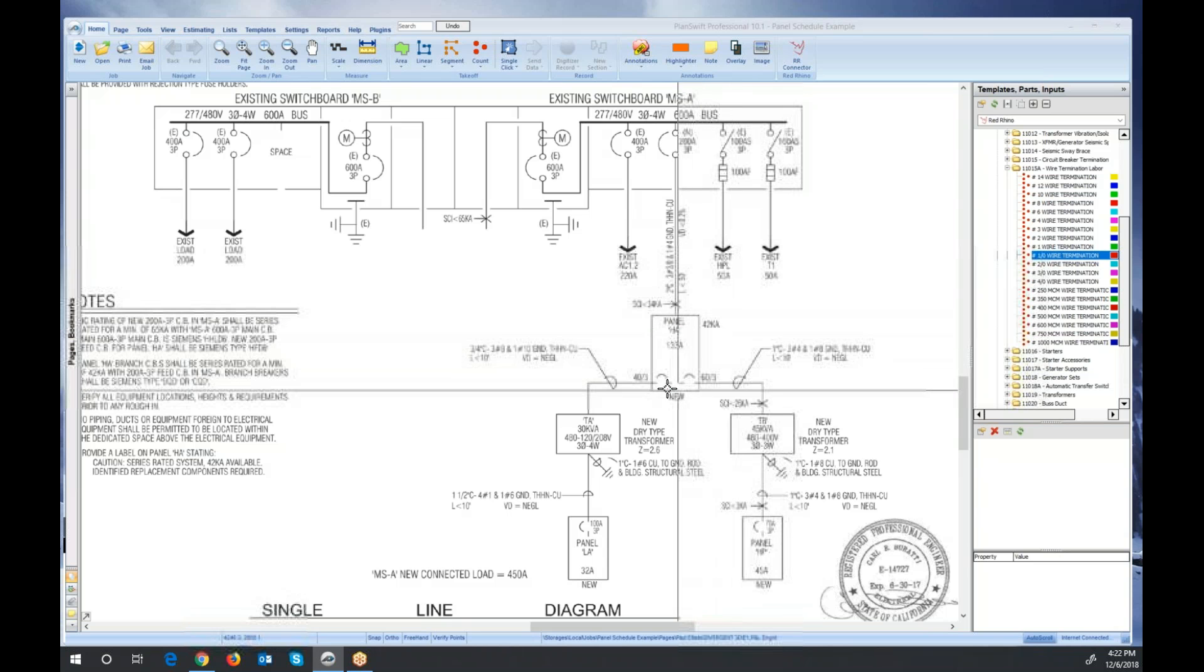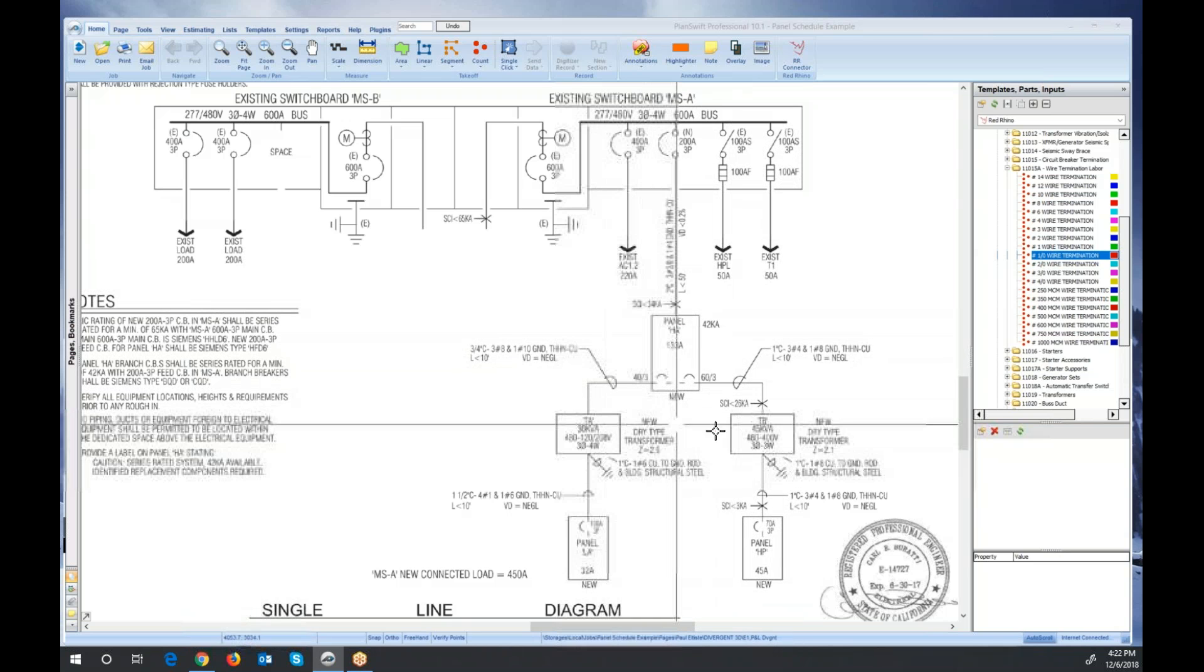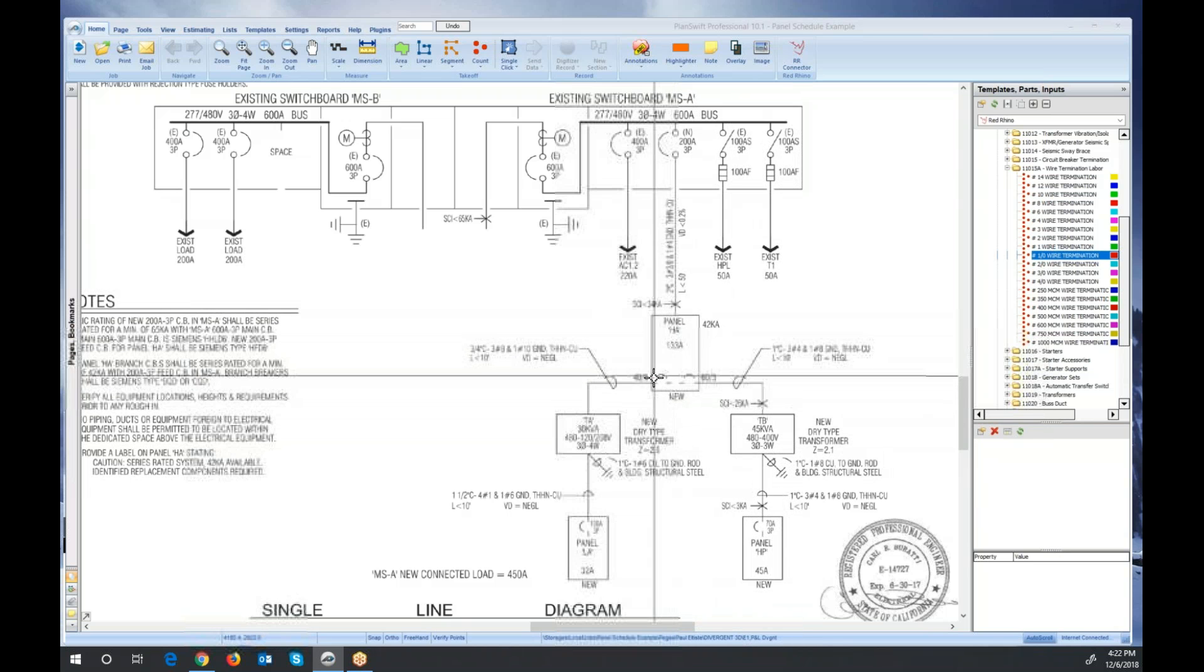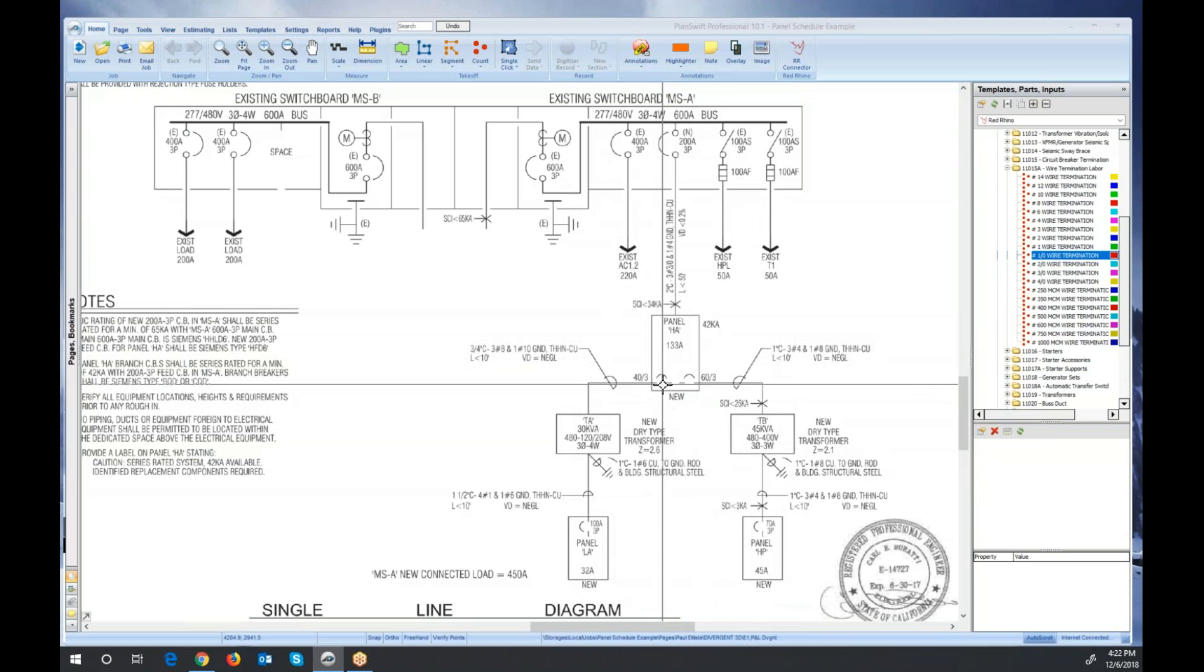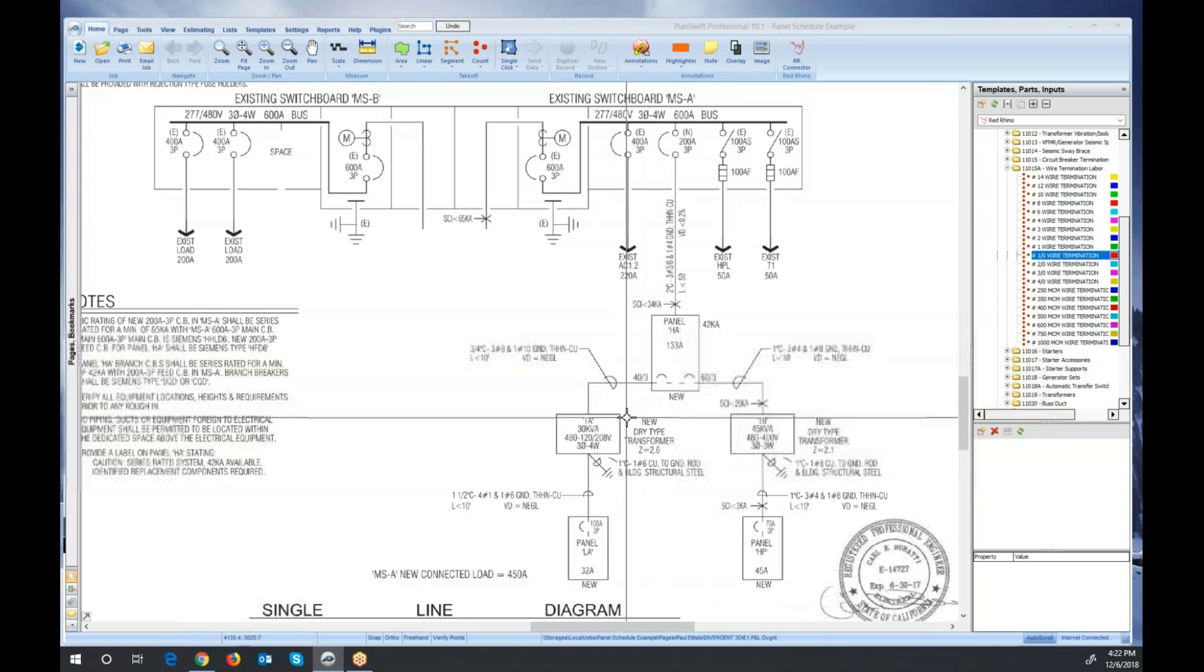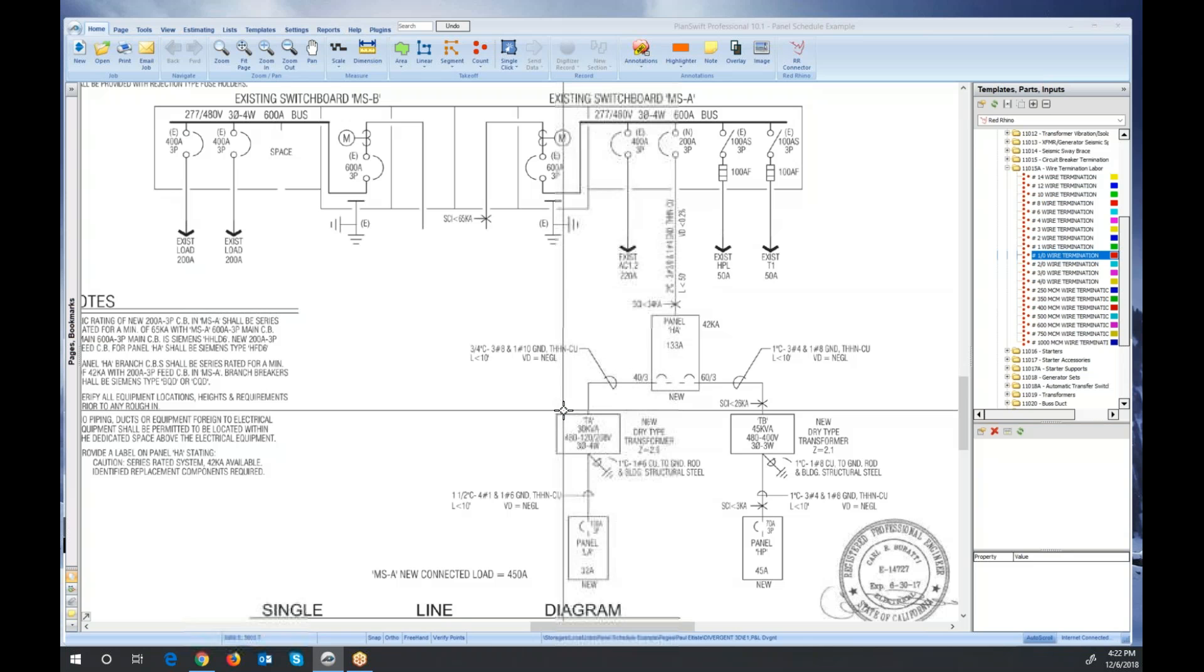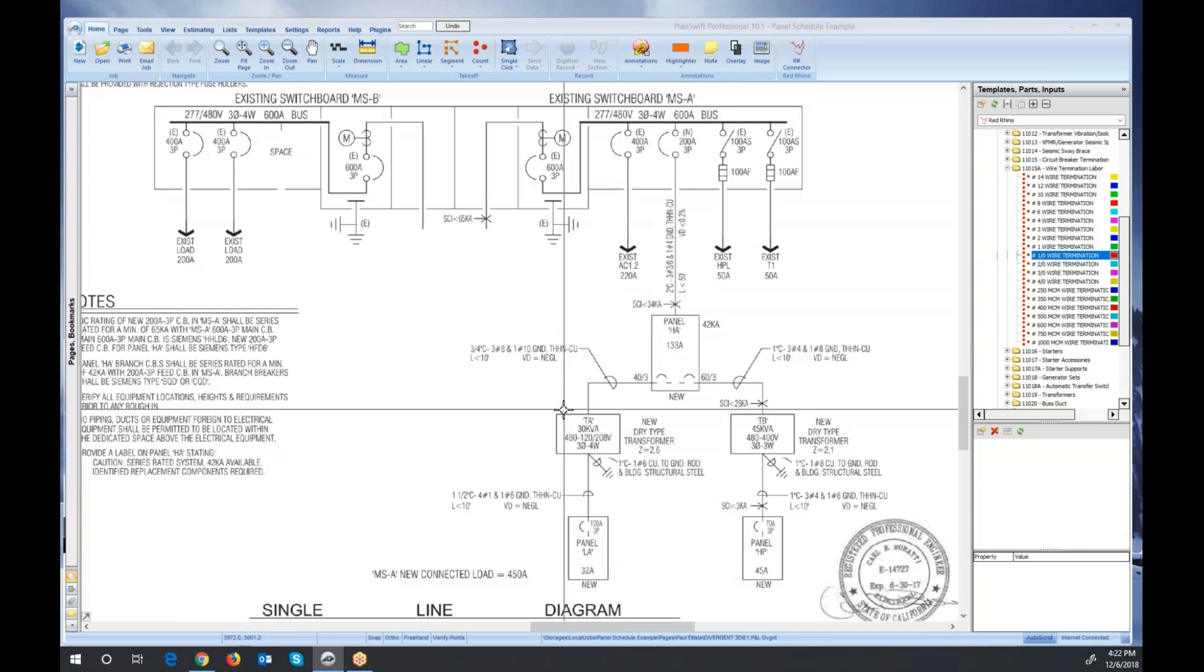Here's another one. This panel feeds two different transformers. See that? It shows a circuit breaker in the panel. But the transformers would need wire termination labor. Now there's more to it than that. You'd actually want to go add lugs for that transformer also because lugs don't come with transformers.